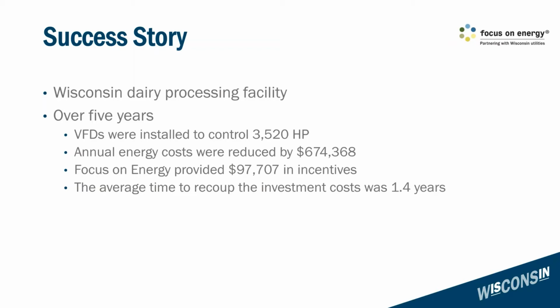They save an annual cost of about $674,000 based on our energy savings predictions, and over the 5 years they also got close to $98,000 in Focus on Energy incentives. When you look at all the VFDs they've installed, the average time to recoup the investment was just under 1.5 years, so it's very cost effective and worthwhile. The facility actually has an entire room just dedicated to all their VFDs.